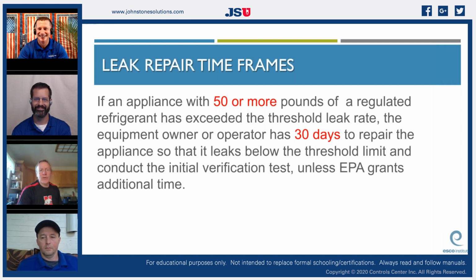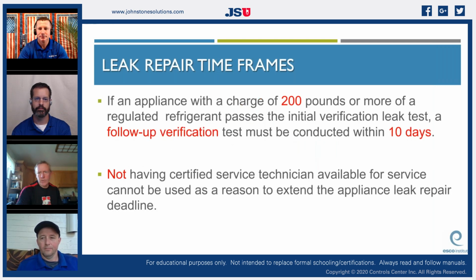Yeah, that's right. So, if an appliance with 50 or more pounds of a regulated refrigerant exceeds the threshold leak rate, the equipment owner or operator has 30 days to repair the appliance and conduct an initial verification test. If an appliance has a charge of 200 pounds or more of a regulated refrigerant, you have 10 days to do a follow-up verification on it. And again, this PowerPoint isn't just here to help you pass Type 2 of the EPA exam.